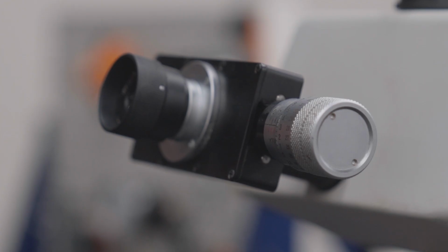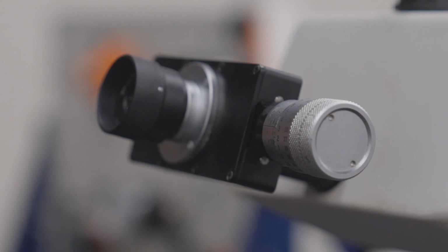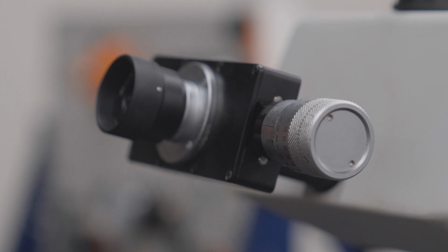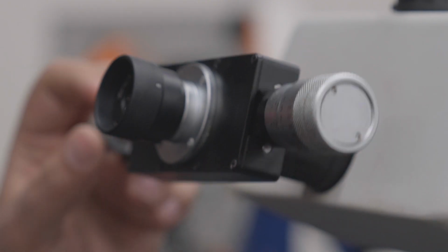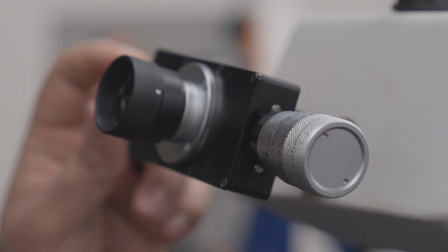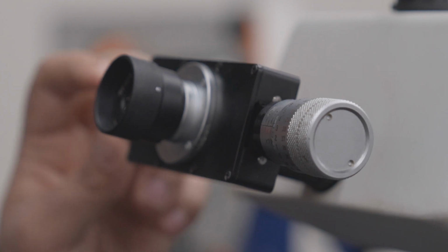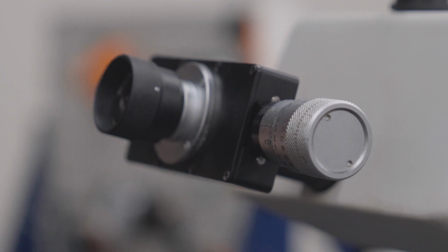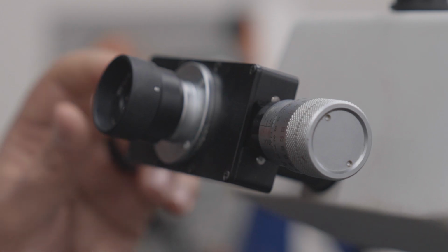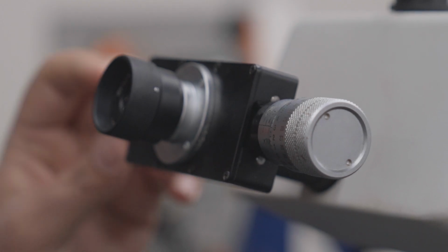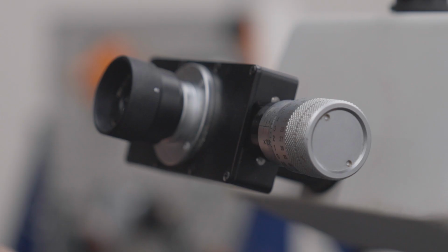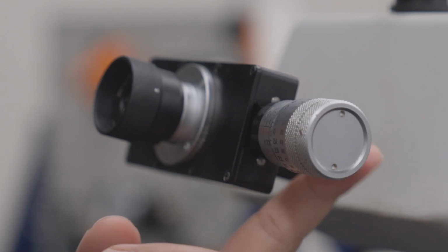When you're done with the loading, you want to go to the M40 lens that we have there. You want to move the turret to the M40 lens. You also want to make sure that you don't move your sample, otherwise you won't be able to find your indents, right? And then we have 2 knobs on the visor. If you look into the visor, you're going to see 2 lines. One of the knobs moves the 2 lines with each other, the knob on the left, and the other knob is going to help you make the measurement.